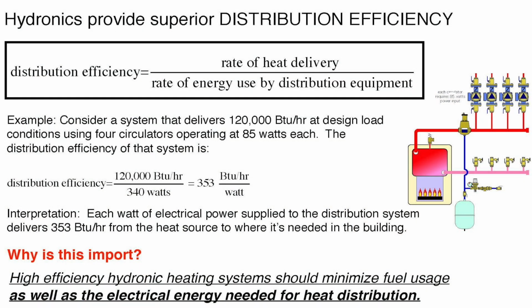So I mentioned distribution efficiency. I just want to do a quick comparison. You just take rate of heat delivery, divide it by wattage going into your distribution system. So really quick, here's a very common hydronic system, boiler, 4 zone circulators. If we said each zone circulator is 85 watts, and all 4 of them were running, and then we're moving 120,000 BTUs per hour, there's the math. It's really simple. So we get this number, 353 BTUs per hour per watt.